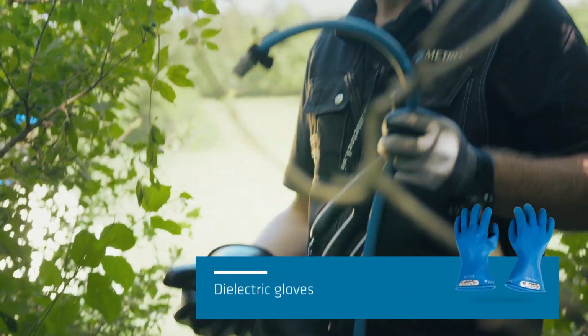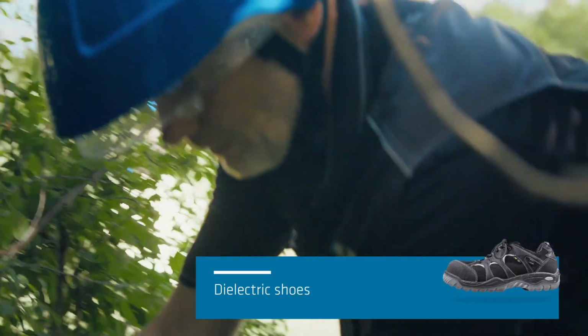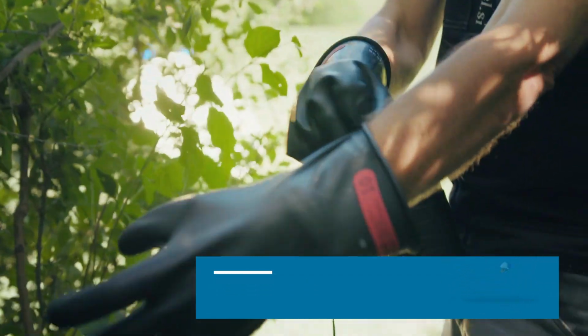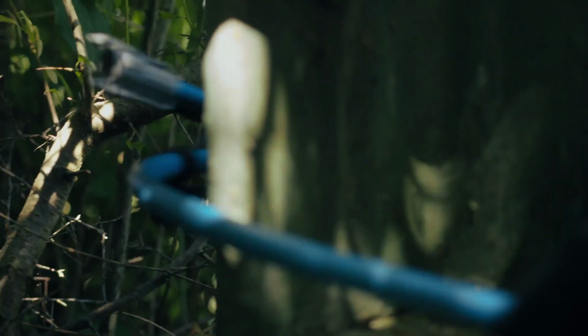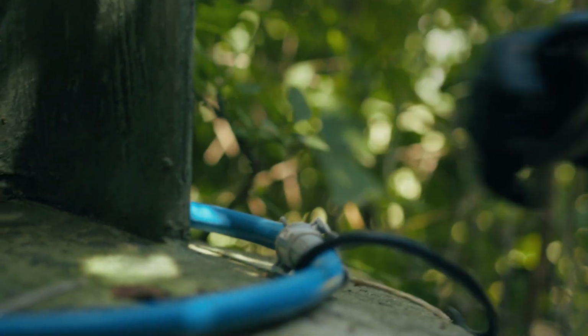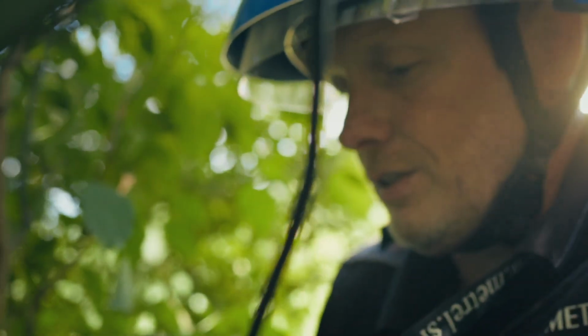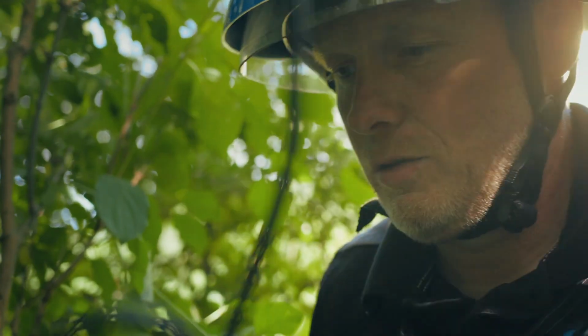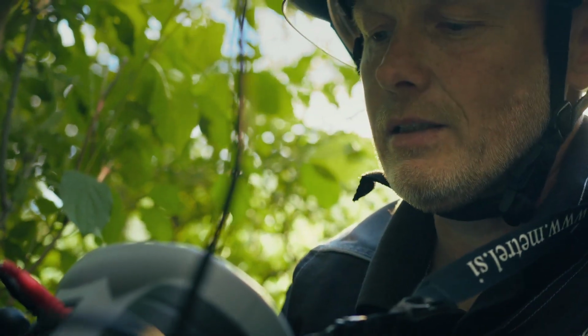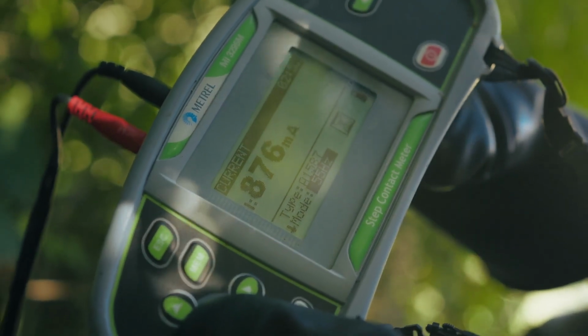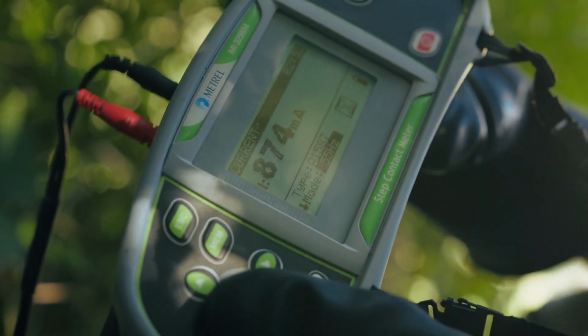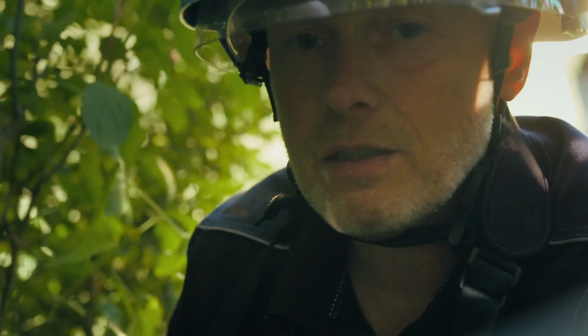So the first measurement would be the current measurement of a separate leg. First we connect the flex clamp and we measure the current, which is very close to 10 milliamps. The complete current to the tower is, we can check. So we remove the flex clamps to the input circuit, and we can see that the total current is around 876 milliamps. It is stable current. And now we can again measure a separate leg to establish where this current flows. From those results, we will also get the information about the split factor of this tower.